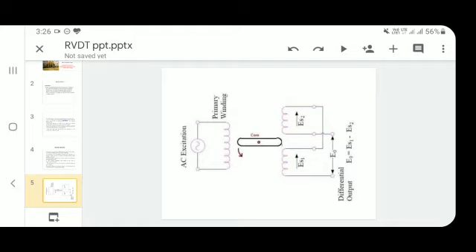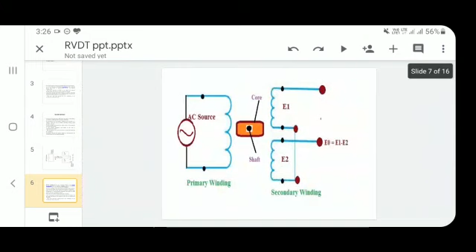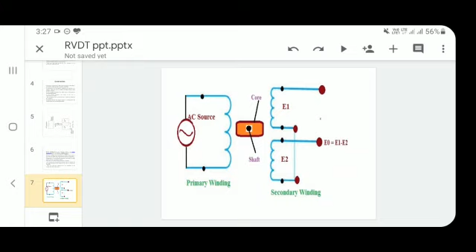RVDT transducer has windings similar to a normal transformer, such as a primary winding and two secondary windings. These windings are shown in the RVDT diagram. The two secondary windings have an equal number of turns and are located on both sides of the primary winding of the transformer. A cam-shaped magnetic core made of soft iron is coupled to a shaft. The core will turn between the two windings of the transformer due to the shaft. This is again showing the diagram, primary winding and the secondary winding.